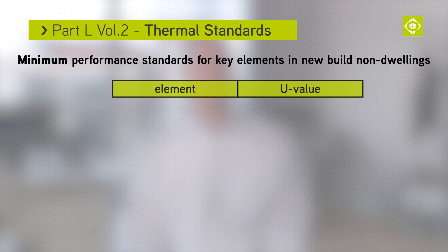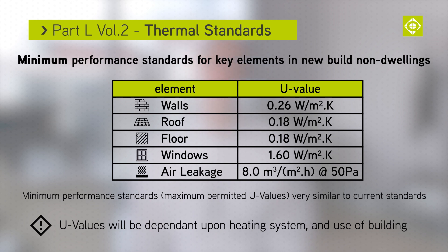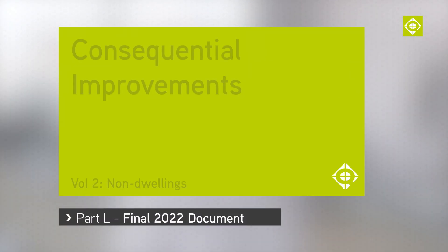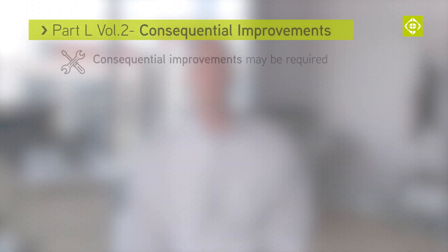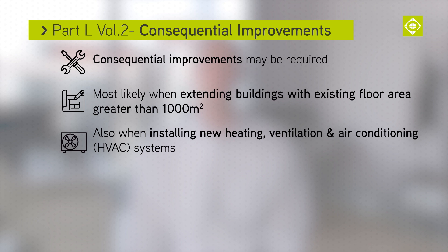Maximum permitted U-values for new build non-dwellings are shown on screen — these are very similar to the current standards. The U-values will be dependent upon the use of the building and the heating systems installed, and the same values apply to new thermal elements in non-domestic extensions. Consequential improvements might also be necessary, primarily when extending buildings with an existing floor area greater than 1000m², and when installing new HVAC systems for the first time or increasing the capacity of any existing HVAC systems within the building.